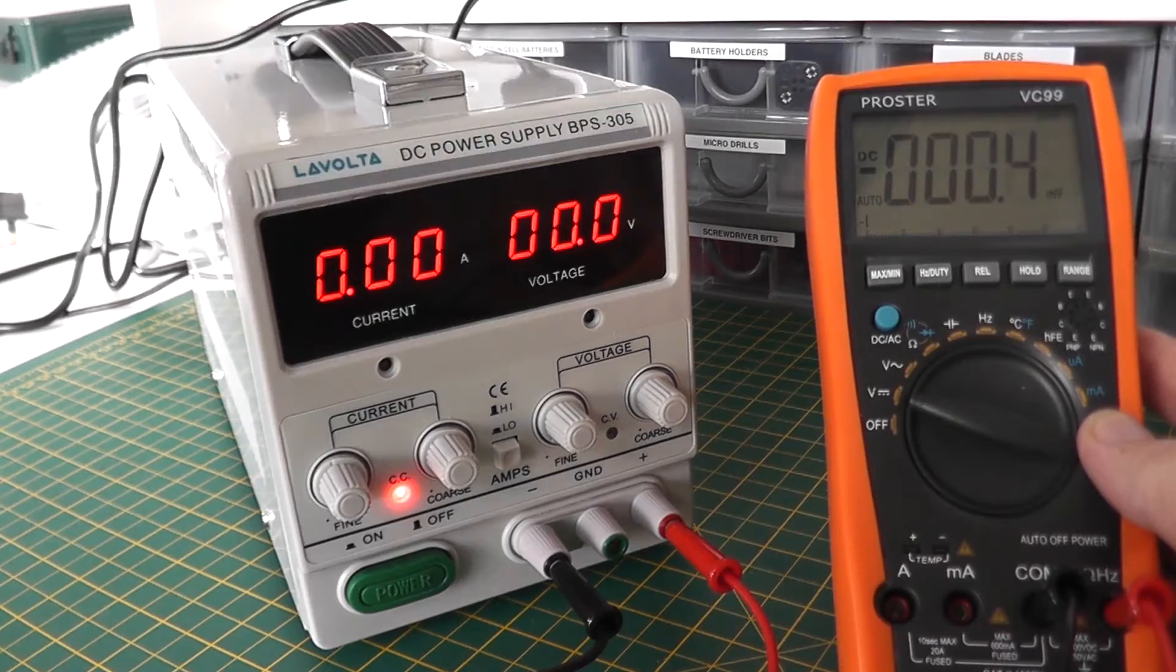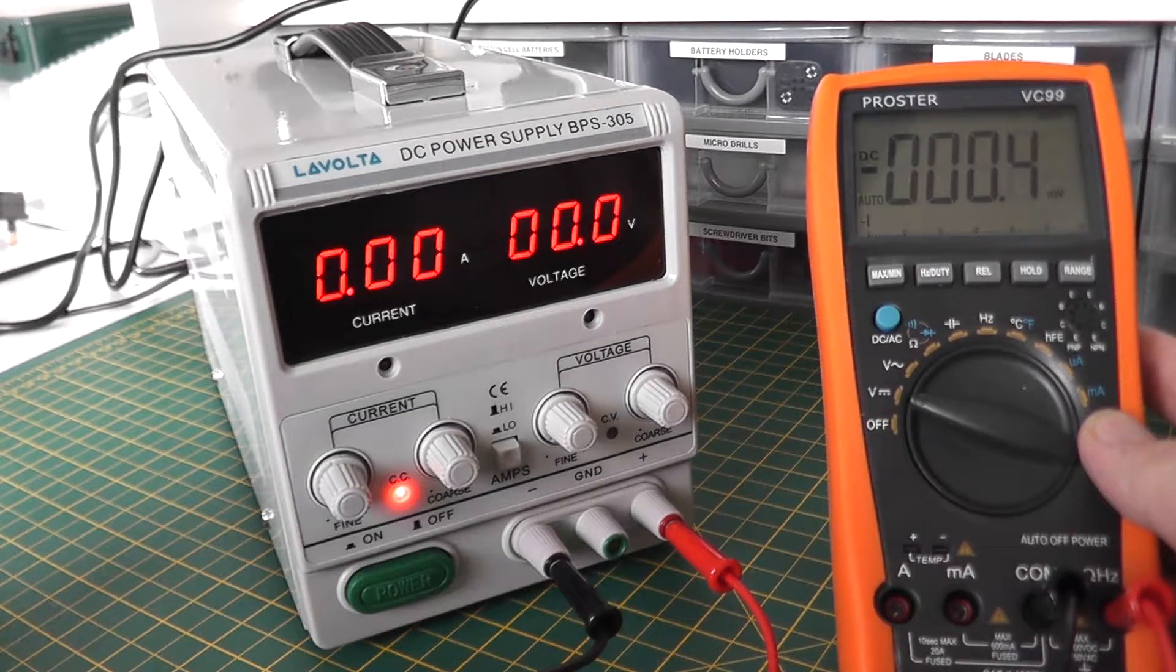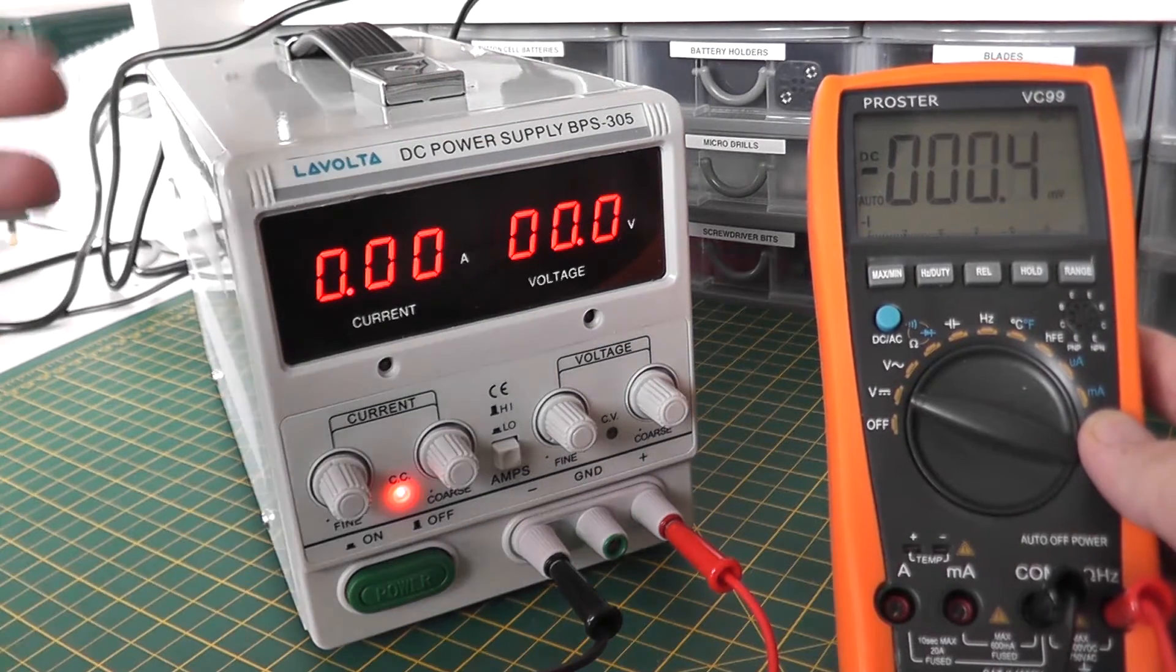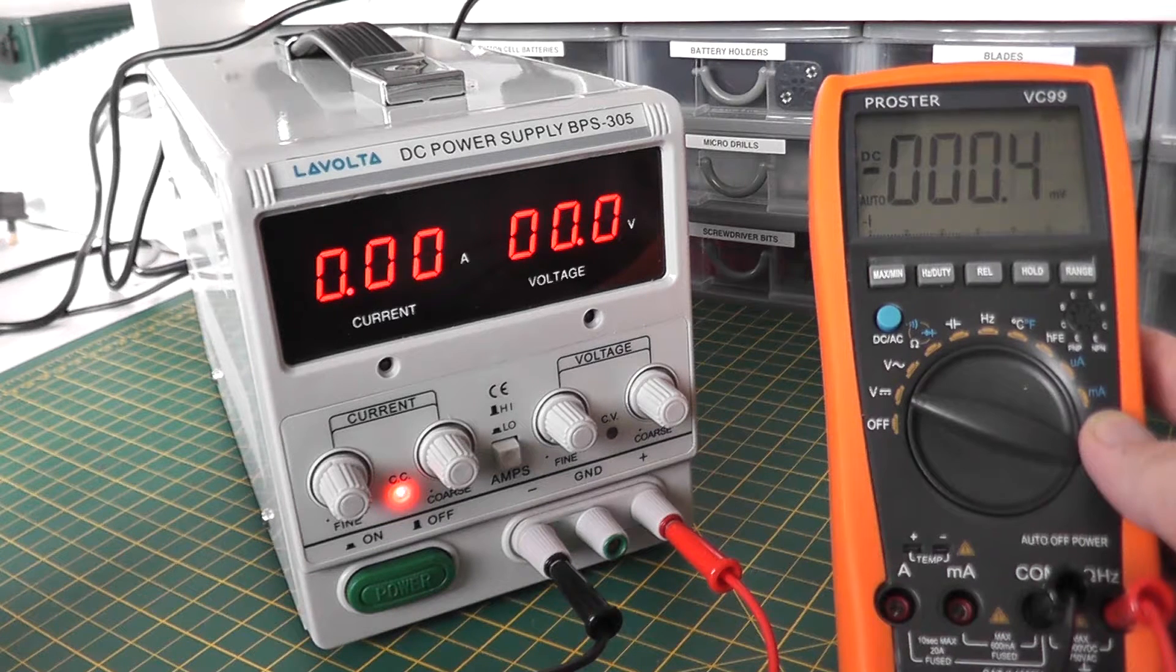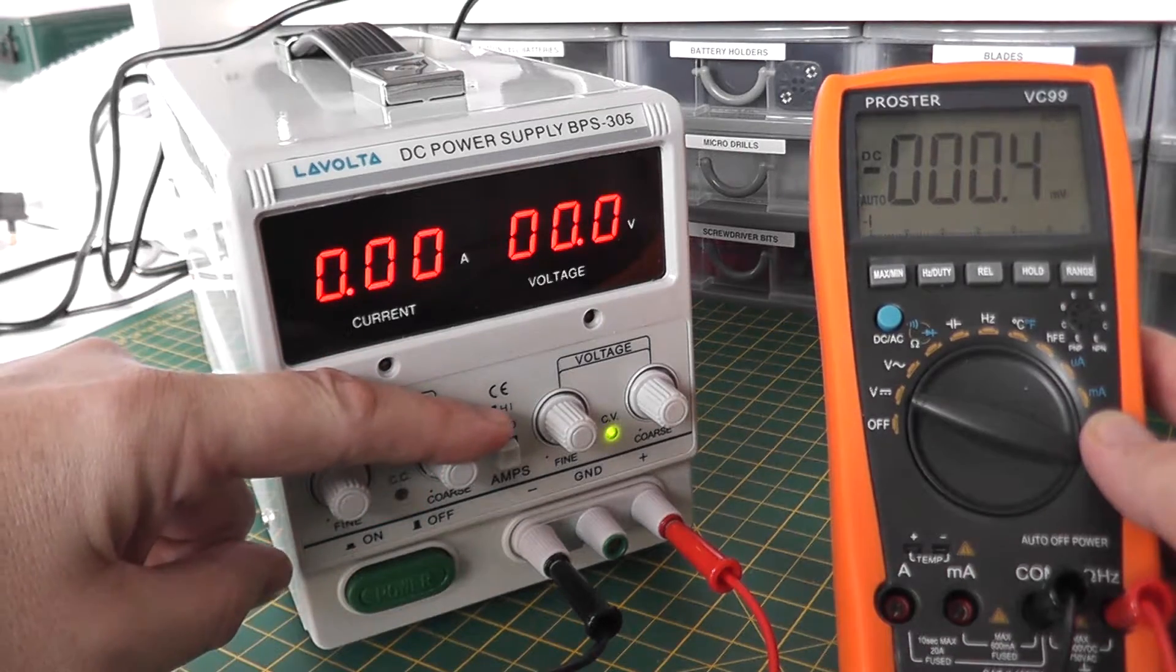As I've said there are two controls, a coarse control and a fine control. Basically the coarse control increases the voltage in larger steps and the fine control allows you to fine tune those steps to a more accurate voltage. So let's apply a little bit of current, not very much but a little bit, and let's turn the voltage.